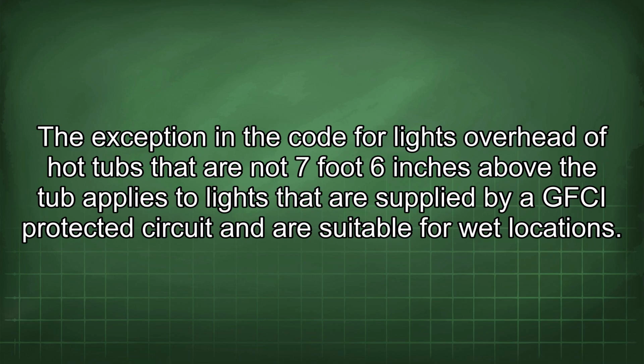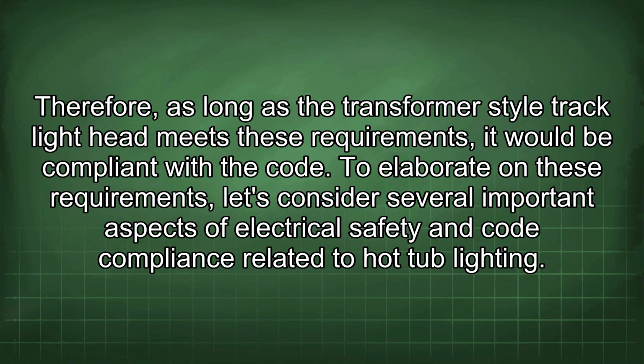The exception in the code for lights overhead of hot tubs that are not 7 foot 6 inches above the tub applies to lights that are supplied by a GFCI protected circuit and are suitable for wet locations. Therefore, as long as the transformer-style track light head meets these requirements, it would be compliant with the code.